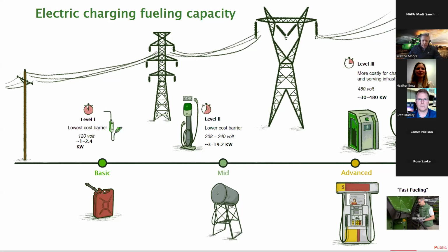Level 2 gets to that 240 volt. It's still a single phase connection. It gets up to an 80 amp circuit that can provide about 19 kilowatts of charge power to a vehicle. That would be kind of the mid-level, like a site that has a little bit of fuel storage. It's something that can get you by for a small amount of time, but it's not going to run a full operation off of.